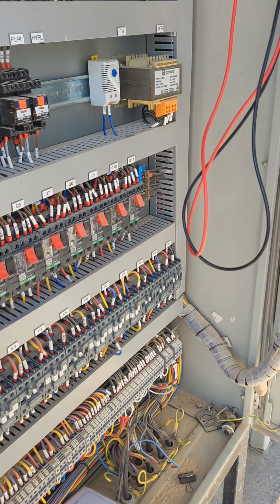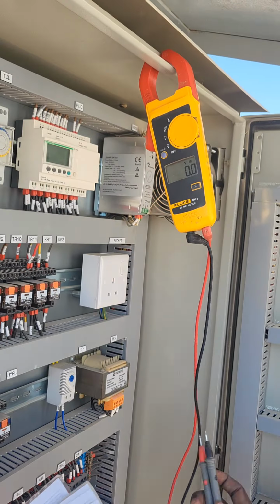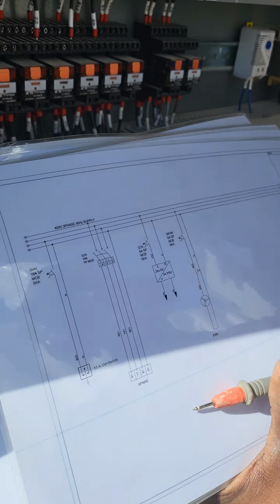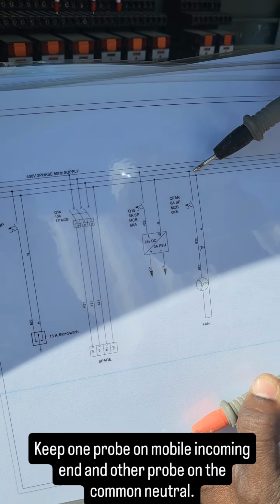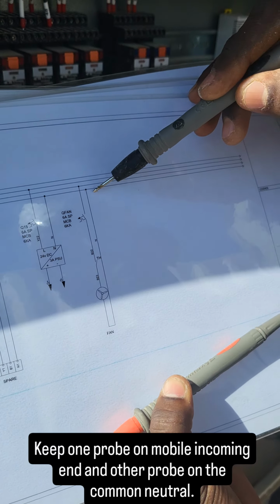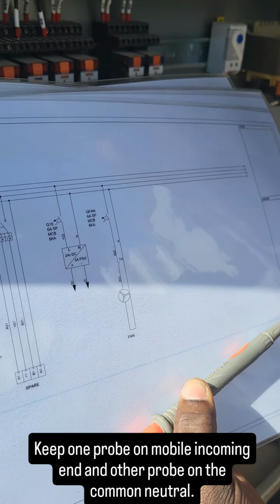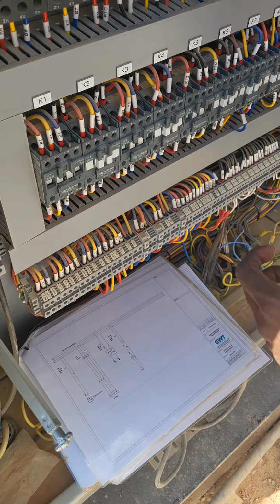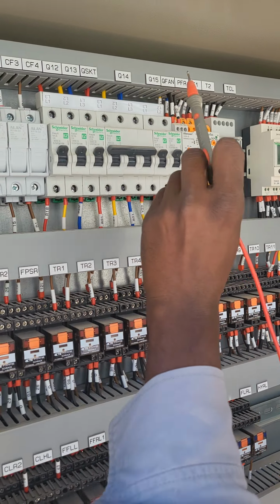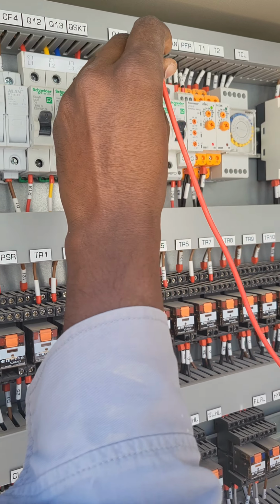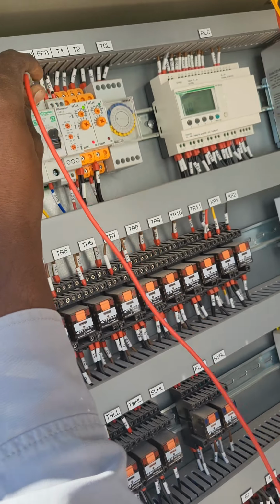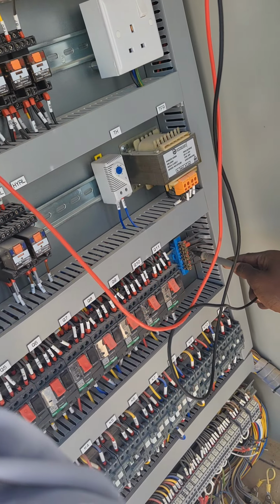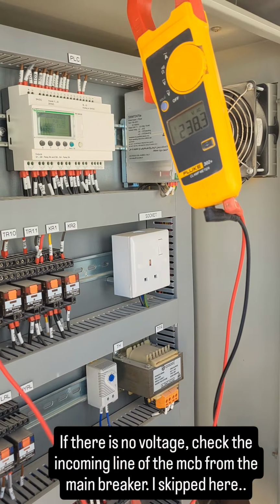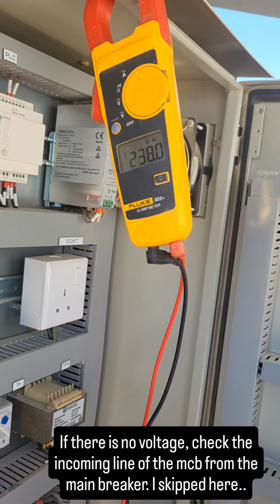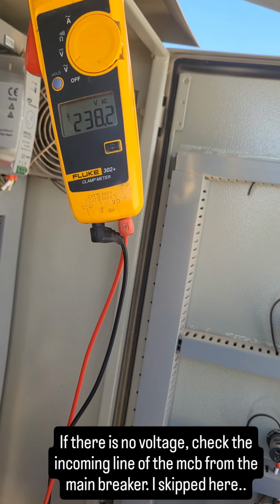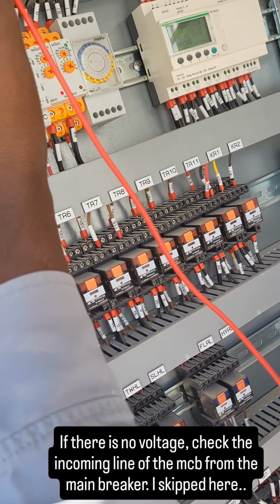Now we will clamp the multimeter to the panel so that it will be easy for us. Now keep one probe on the MCB incoming supply and another probe on the neutral, so that we can take neutral as common. I will show you how. Now here is the Q fan MCB, and we keep one probe on the incoming of the Q fan MCB, another probe on the neutral, which is common. Then check the voltage. It is 238 volt AC, so it means it is receiving power supply on the incoming end of the MCB.